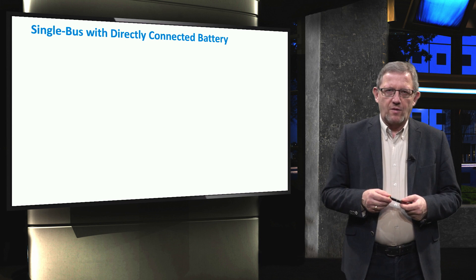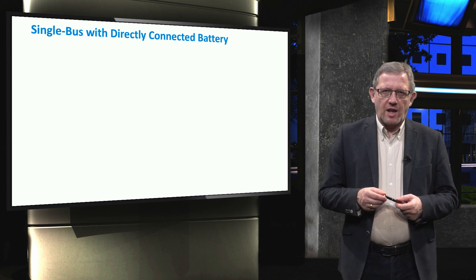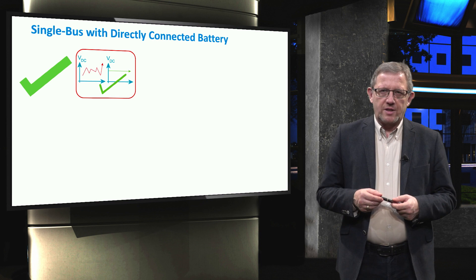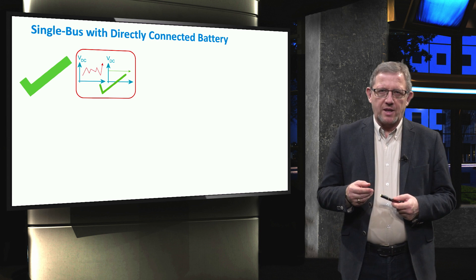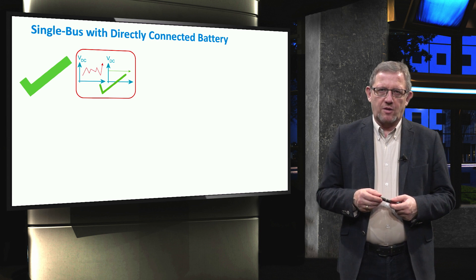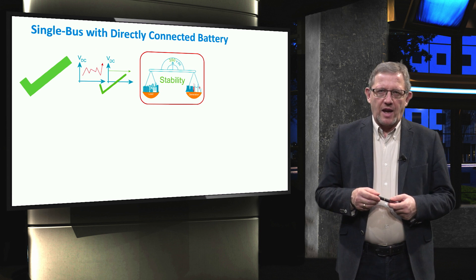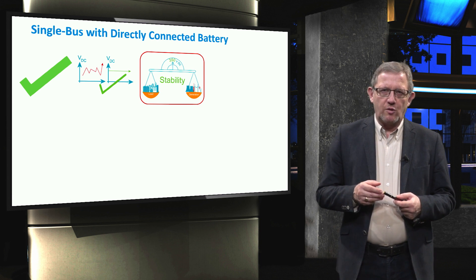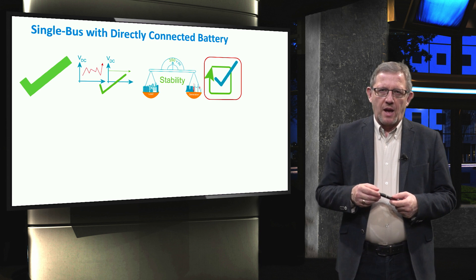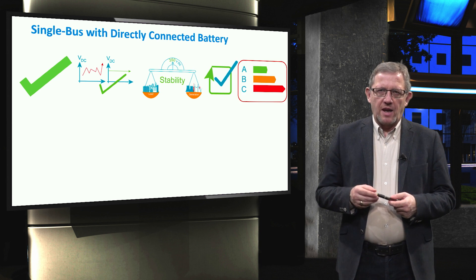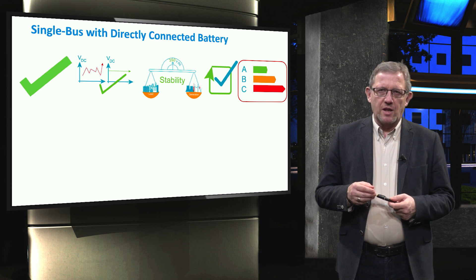The single bus with directly connected battery has a number of advantages. First, due to the direct connection of the battery, the DC link voltage is very stable and regulated because the battery acts as a very large capacitor. This also results in overall higher stability, satisfactorily matching power mismatch between generating units and the loads. The reliability is also increased. Finally, as the battery is directly connected to the DC link without power converters, the overall electrical efficiency is also higher.